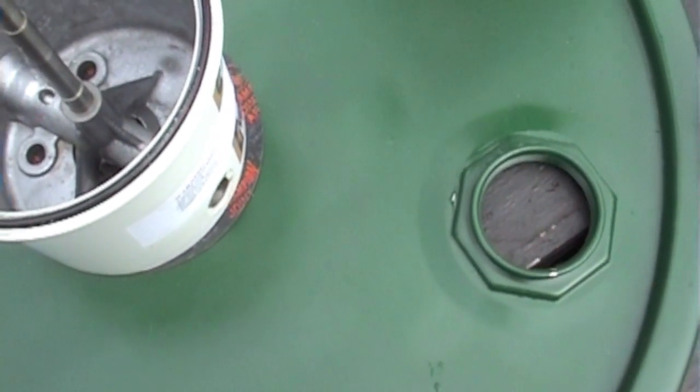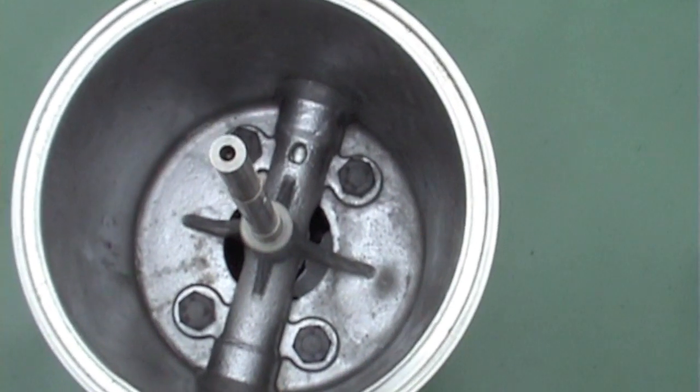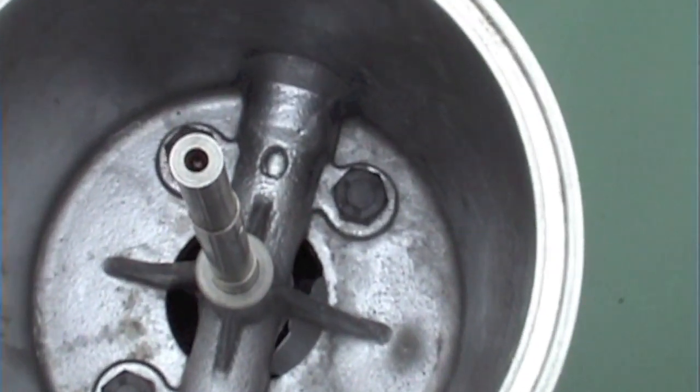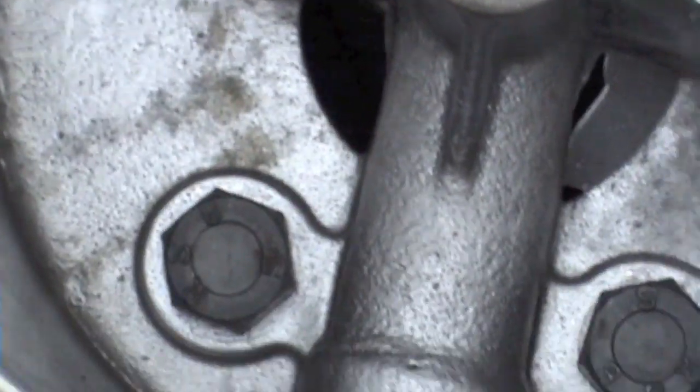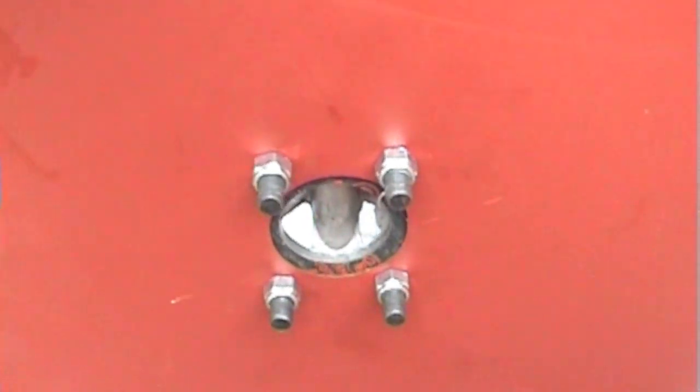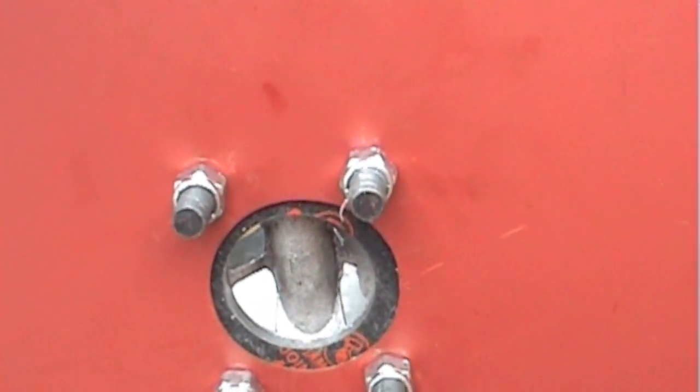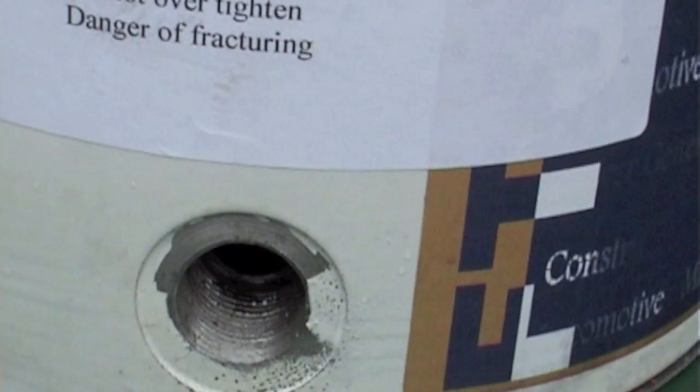Pressure gauge onto your pump. I've screwed them on tight, five-eighths nut and bolt. And then what happens here, clean oil comes through there. On the centrifuge, do not tighten this bolt up too tight else you will crack the casing.